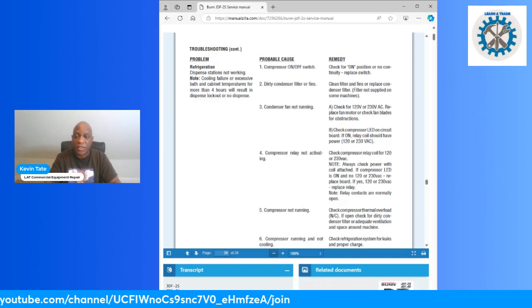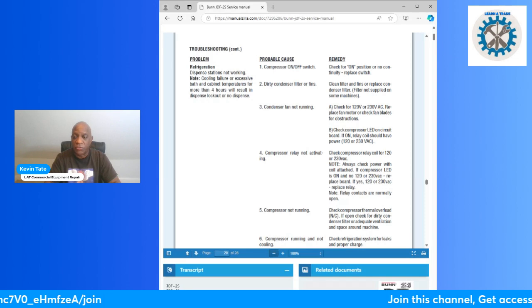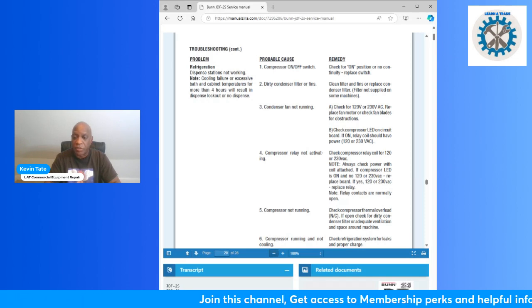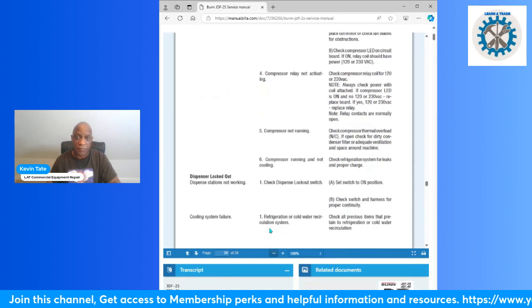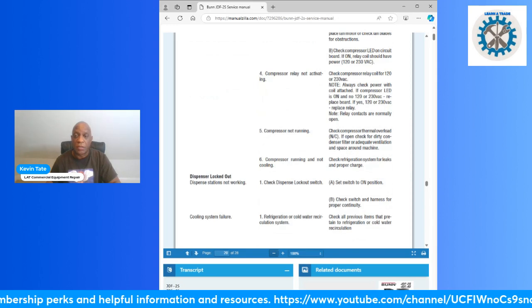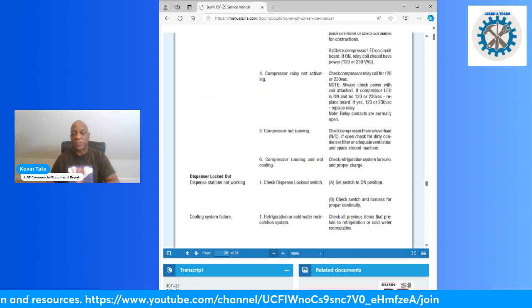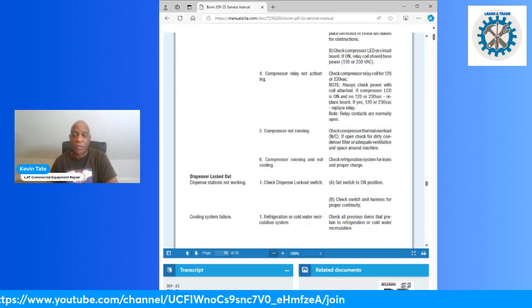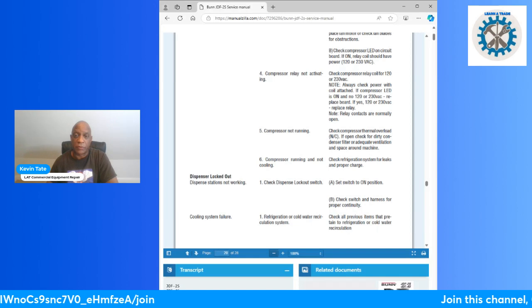The compressor relay could not be activating, so it could be an issue with the compressor relay. The compressor could also not be running due to an internal fault. So that's something you'll have to check out also, as far as checking the legs on the compressor, your terminals.